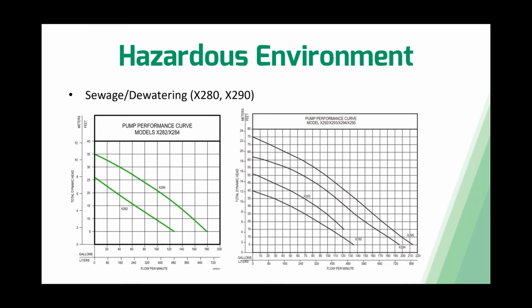Same thing here, just would like to show you the difference in the pump performances and the broad offering within the X280s and the X290 series. If you're looking at the X280 series, the 284, which is the 1 horsepower version of that, can get out to 180 gallons per minute, go up to 35 foot of head. And then when you go to the X290 series, with the X295 being the biggest pump there, you can get heads up to around 75 foot of head. On the lower end of the curve, you can get performances up to 210 gallons per minute, anywhere from 5 to 10 feet of head.